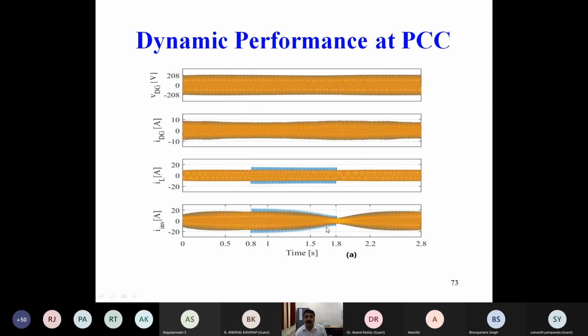Dynamic performance at PCC: you can see here the inverter current, how it is changing and then it is managing. Here you can see the load current, one phase has increased current. Here you can see the inverter current has increased for that particular instance and then it has managed, it has maintained. Here you can see the DG, at this point the DG is having lower current, then it has increased, that means it has started supplying the increase in current.